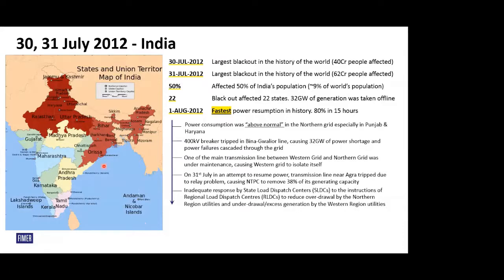Then because of this overloading, a 400 kV breaker tripped in the Bina Gwalior line and 32 gigawatt of power went offline. This caused a cascade of trippings. Ideally, if the 11 kV is overloaded, only the 11 kV should get isolated, or 66 kV, or if there's 110 or 132, that has to get tripped, then 220, then 400. But unfortunately here, because probably the relays were widened to take this agricultural overload, the entire load was transferred and the 400 kV breaker tripped, whereas the downstream breakers did not trip.